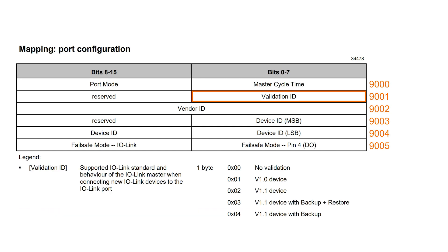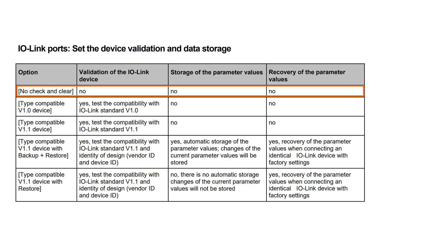The next parameter to be set is the validation ID. To explain the five options available, let's look at another excerpt from the IO-Link Master Device Manual. The first option, No Check and Clear, allows any IO-Link device to be connected to the port and read. This means that there is no device check and no data storage.